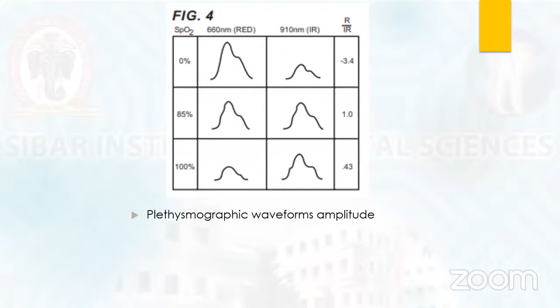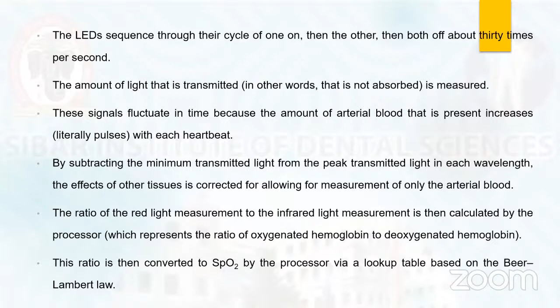Always, when the LED operates, it goes on and off. So the red light comes on, the infrared light comes on, and then both go off. It does this 30 times per second. So there is no continuous illumination, there is on and off, and the light that is transmitted through the tissue, not the reflected one, is taken up by the detector.